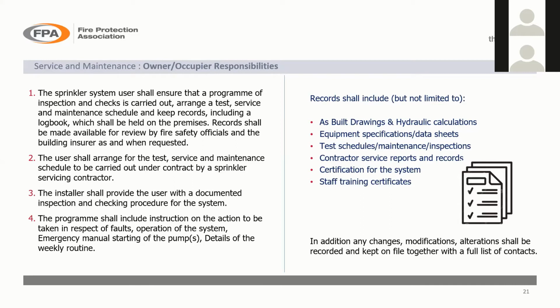The kind of records that you should have on site, as Dale explained in the first part, and it's not limited to this, but you should have as-built drawings and hydraulic calculations. And I think one of the questions that we've had come in relates to this. If you inherit a system without any kind of drawings or anything else, well, there's a few routes you can go down to try and get them. You can approach the installing company if you know who put it in, and see if they've got it. You might be able to go to the BRE and see if you can trace the system installer, perhaps through the certification scheme. If it's 1048 scheme, you might be able to find it that way.